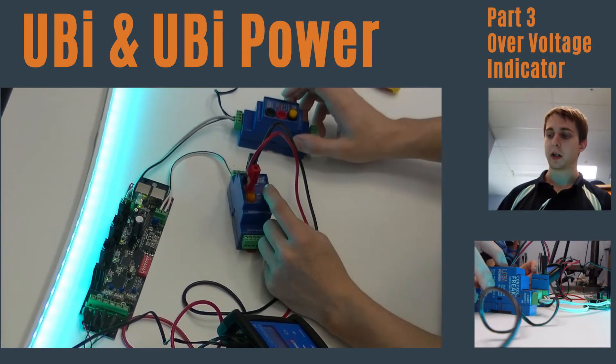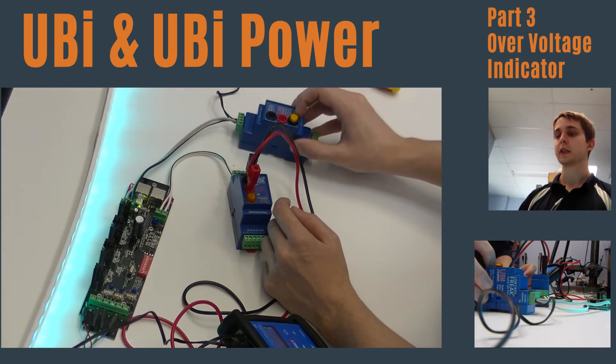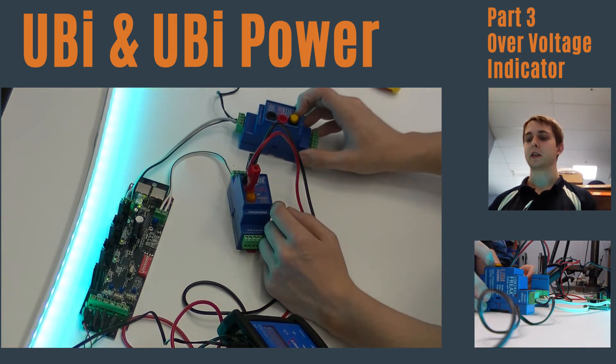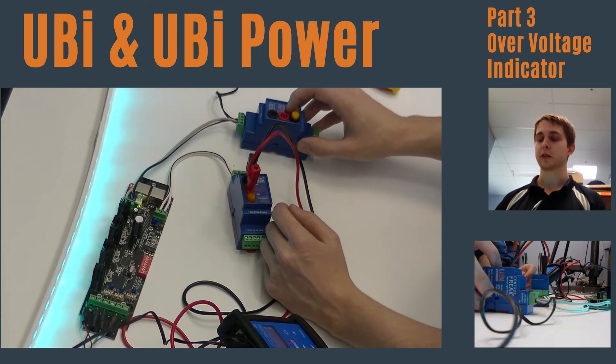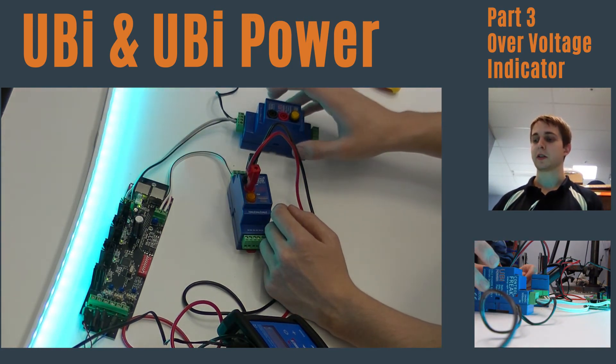Both the UBi and the UBi Power have an indicator on the front of the unit to show when there's over 60 volts on the DALI line. This happens when accidental mains voltage goes onto the DALI line, and it's an indication to turn the system off immediately and not to touch the UBi or UBi Power.